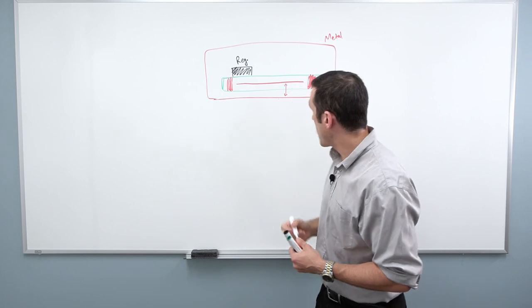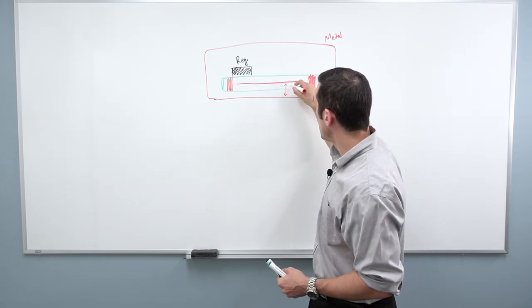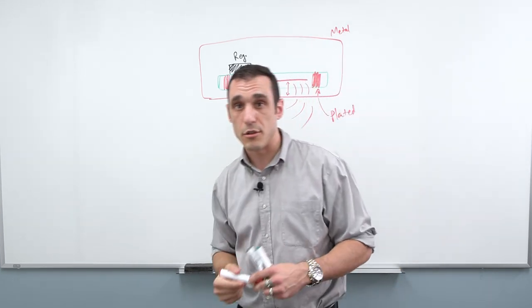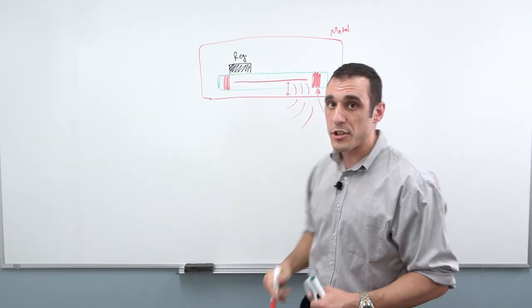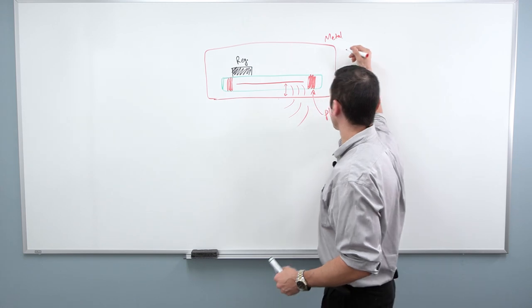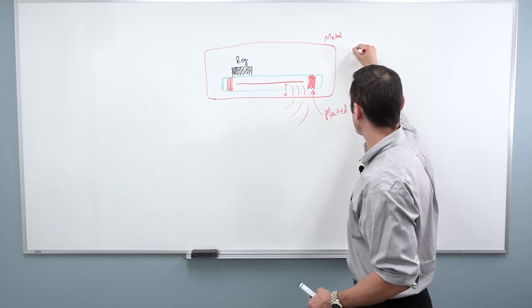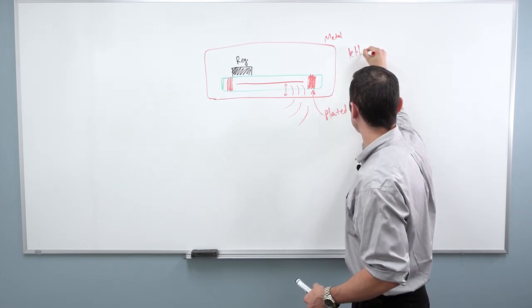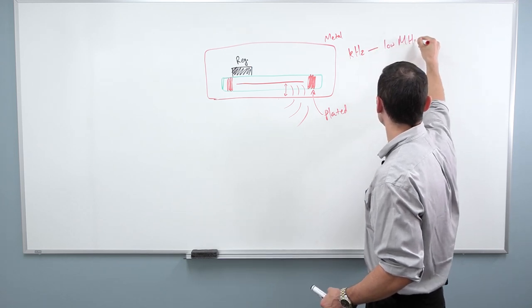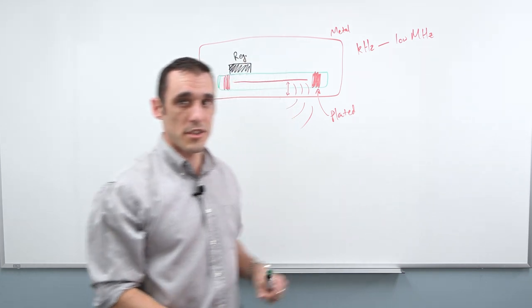And when you have capacitive coupling between the two, you could actually have radiation from the metal enclosure. So failing to ground a big chunky piece of metal in the board or near the board is actually a source of high frequency radiation. Typically for very large metal enclosures, it could be anywhere from kilohertz to low megahertz. And it just all depends on the noise sources that are around.